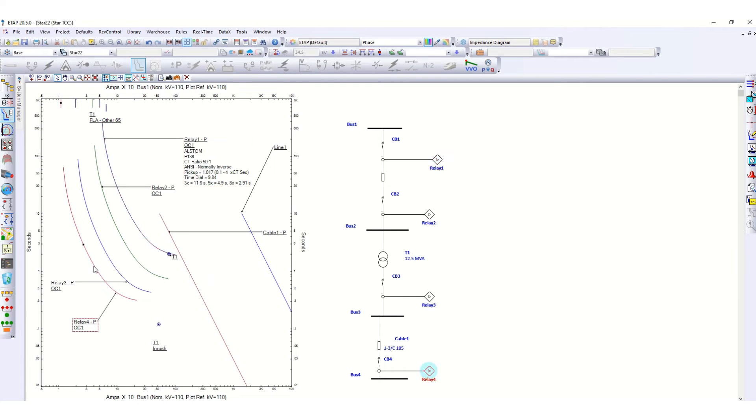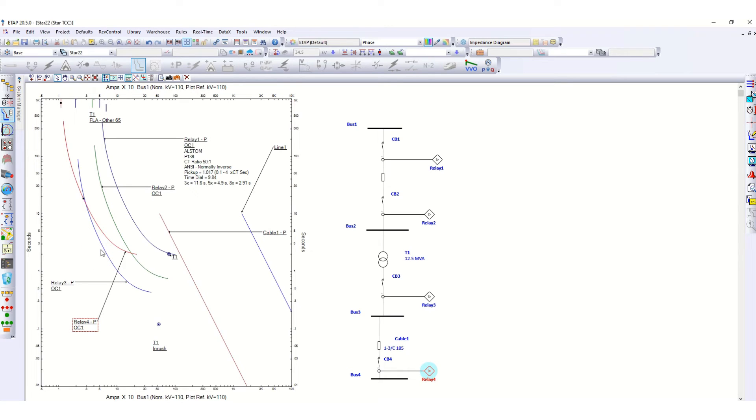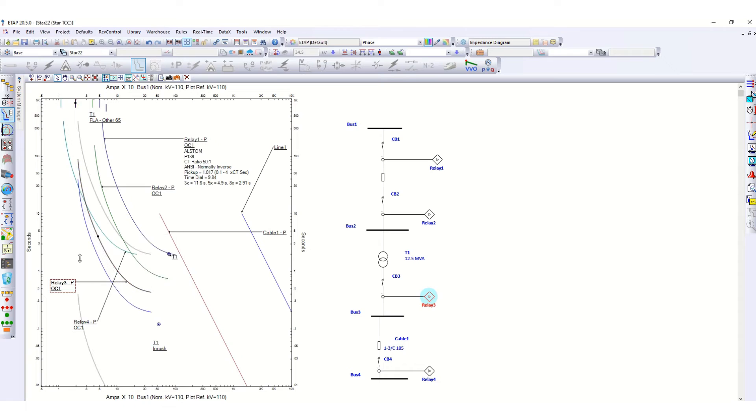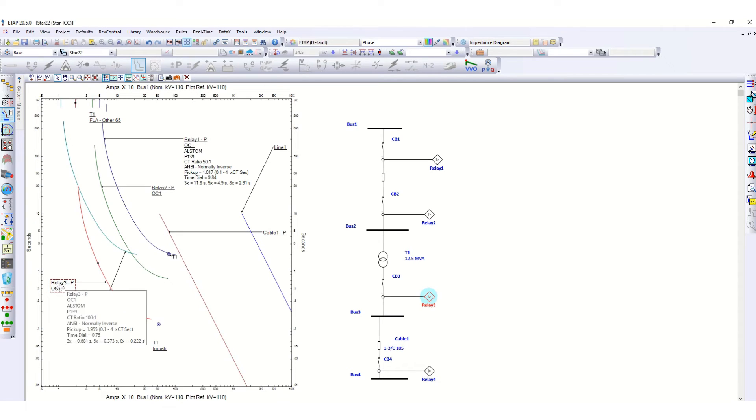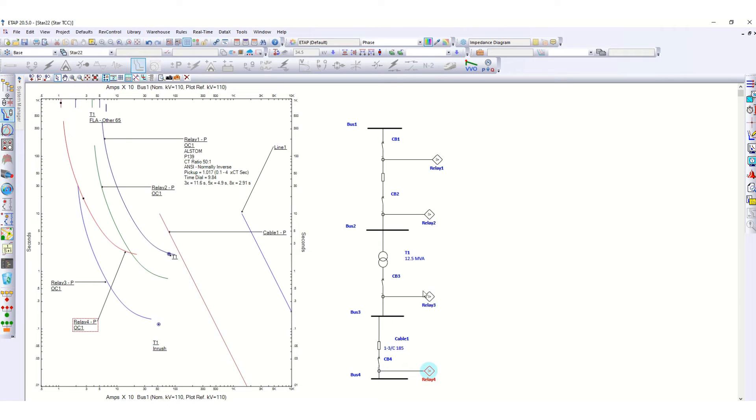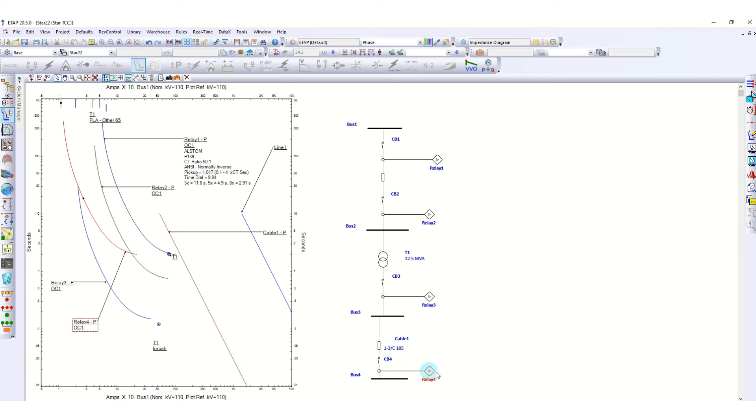If relay 4 moves after relay 3, then this coordination is not proper. In that case, relay 3 will pick up earlier than relay 4. If relay 3 picks up before relay 4, then this coordination is not correct. For proper coordination, we have to select relay 4 action first, that means we have to trip CB4, and then relay 3 as well as CB3.